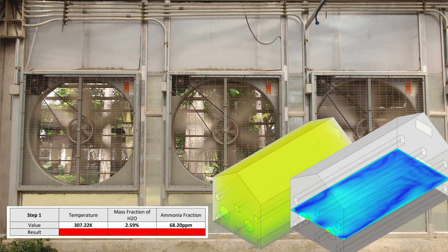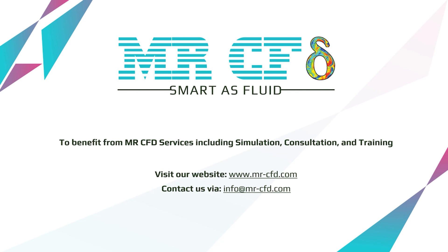Considering the objectives and limitations, we proposed to install the water-cooled air conditioner close to the ceiling. Thus, it would be possible to increase the velocity and benefit from natural convection as well. As a result, all targets were achieved. Importantly, the temperature contour illustrates how the air circulation significantly improved — all rows experienced similar conditions, and the plants were not in direct contact with high-speed airflow, preventing any probable damage.